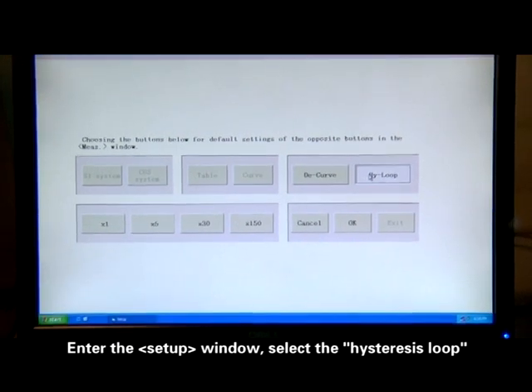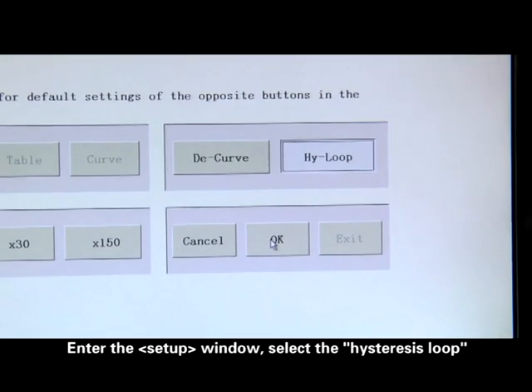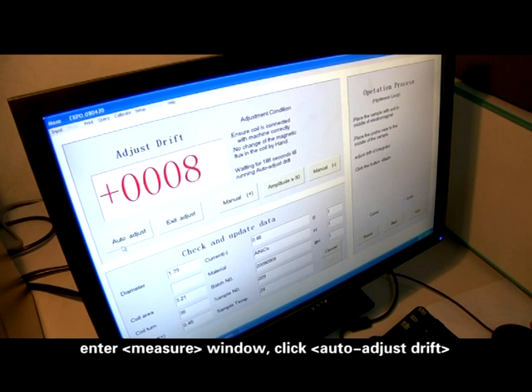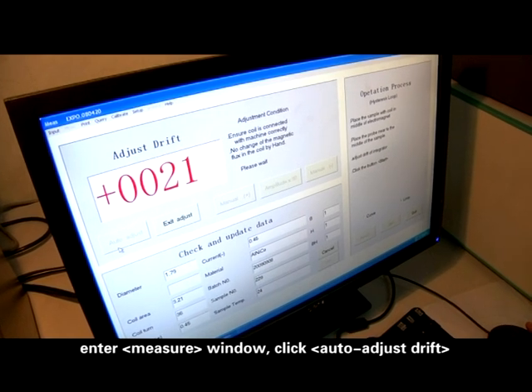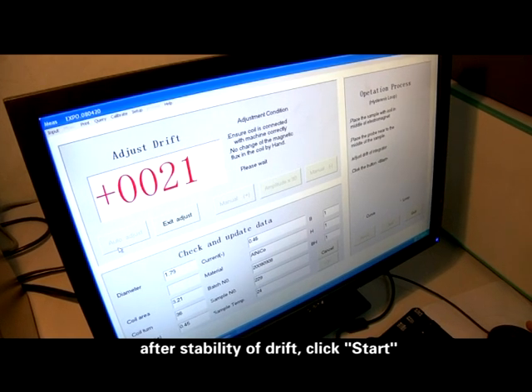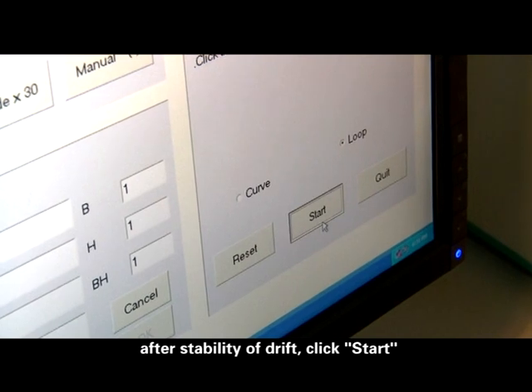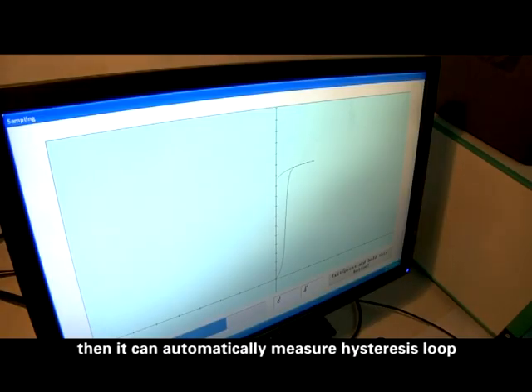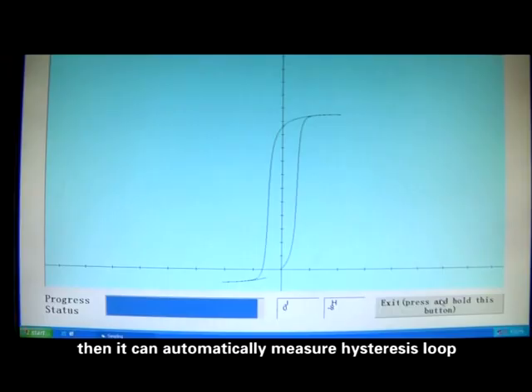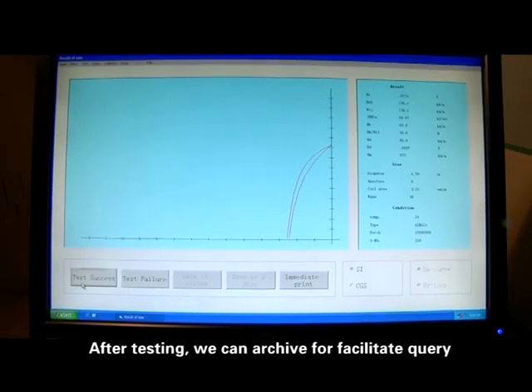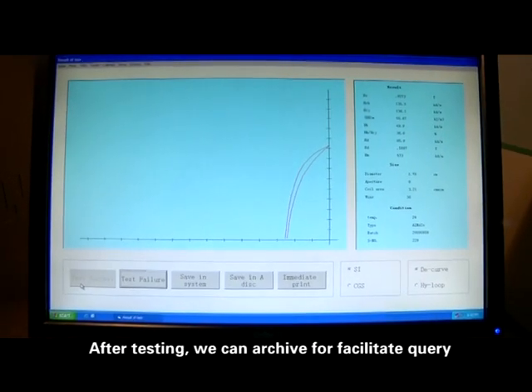Enter the setup window. Select the hysteresis loop. Enter measure window. Click Auto Adjust Drift. After stability of drift, click Start. Then it can automatically measure hysteresis loop. After testing, we can archive for facilitating query.